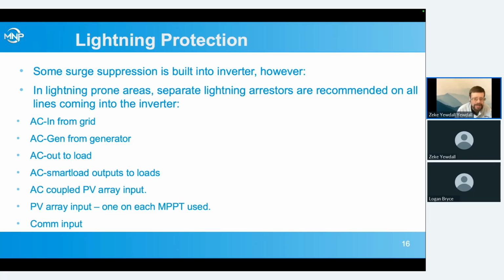So we always recommend extra lightning protection. If you do take a direct strike to the PV array or to the building, even the best lightning protectors may not protect you, but I've actually had a lot of situations where I've taken a direct strike and a majority of the equipment with surge protectors on survived, and the stuff without surge protectors on was just blown into bits. Sometimes it doesn't survive, but it's still got a way better chance if it's got good lightning protection.